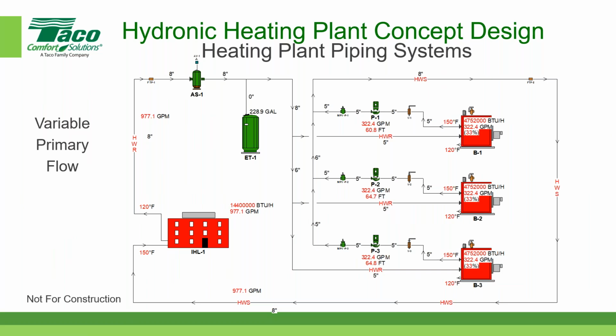Would you use a separate zone with an override to a heat exchanger with the reset controller? That question seems a little wordy. Yeah, there's a variety of ways that you can configure things to accomplish a certain task. So my response is that it's possible to do what you're suggesting. You do have to look at the different variables in your system to see which one makes the most sense. Maybe the boiler water temperature wants to be reset so low on an outdoor air temperature reset that it makes more sense to have a dedicated boiler for domestic hot water. And again, it depends on the type of system. If you have a hotel, for example, a hotel has a huge demand for domestic hot water as compared to an office building, which has very, very little demand for domestic hot water.